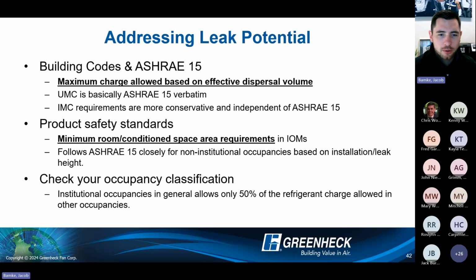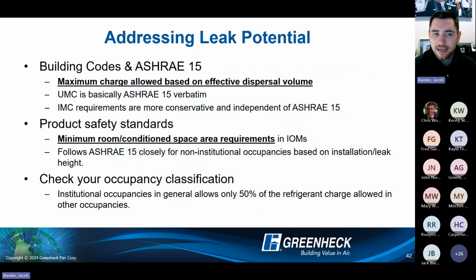And building codes and safety standards are all doing it a little bit differently while also trying to reference each other. So building codes and ASHRAE 15 are specifically looking at a maximum charge allowed based on your effective dispersal volume. So overall, for the area that we can disperse this leaked refrigerant into, there's a maximum charge associated with that. The UMC is basically verbatim with ASHRAE 15. The IMC is a little bit more conservative and independent of ASHRAE 15. So there are some other differences there.